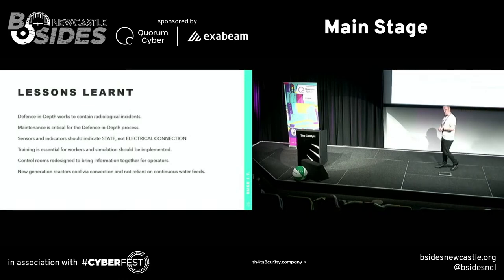Maintenance was absolutely critical to making sure that worked. Sensors and indicators should show the actual state rather than what was commanded — it was only showing the electrical connection, could a current be sent to the valve, rather than confirming the valve was actually closed. One change made to all Generation 2 and then Generation 3 reactors was to actually indicate the true position of the valve.